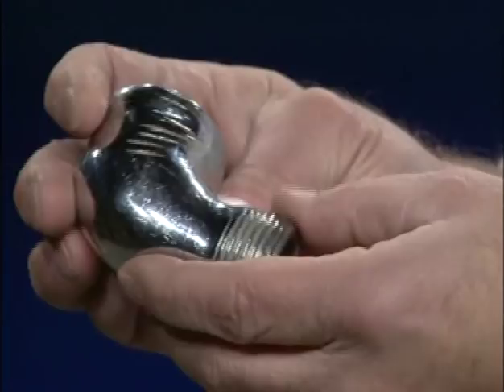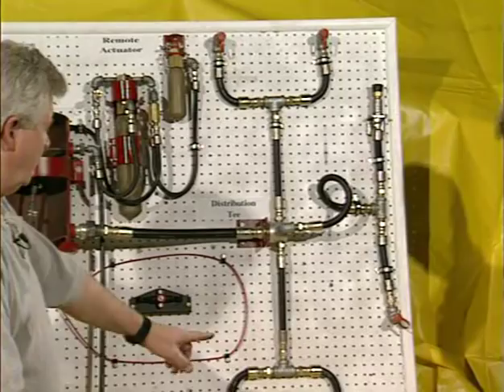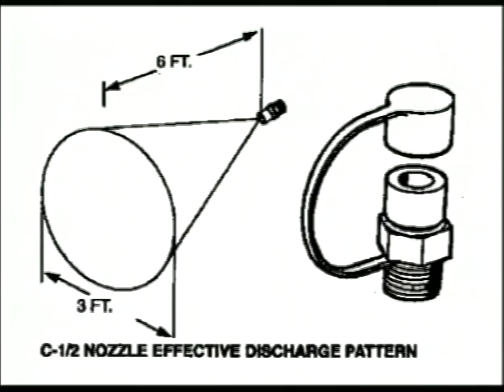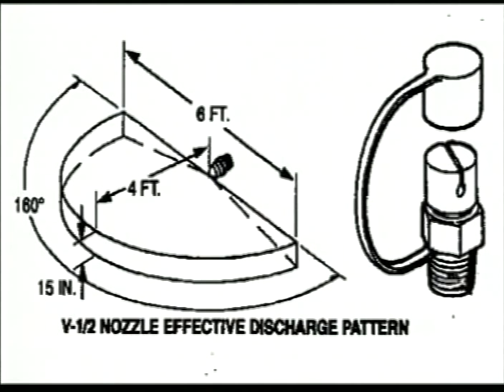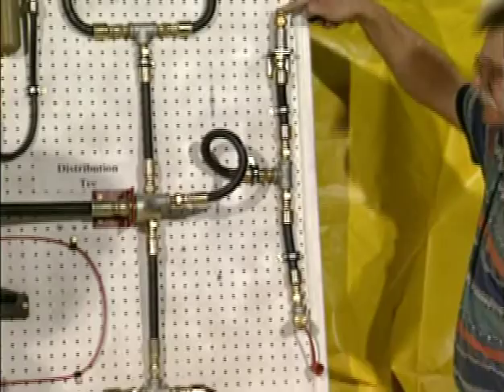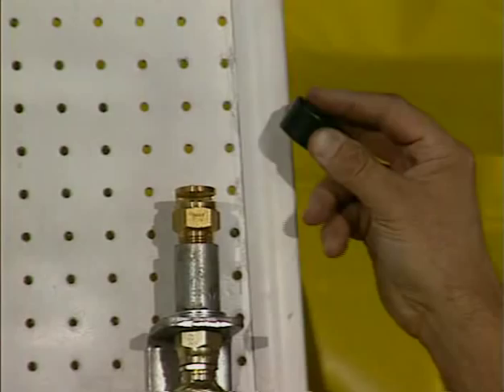From the distribution T, everything is half-inch. There are different nozzles on the Ansul system. The C-nozzle throws out a cone pattern — six feet out and opening to a diameter of 36 inches. The V-half nozzle throws a pattern 36 inches in each direction, opens up to 15 inches, and throws it out four feet. The F-half nozzle throws a flat trajectory that opens up to 15 inches and goes 32 inches in each direction from the nozzle.